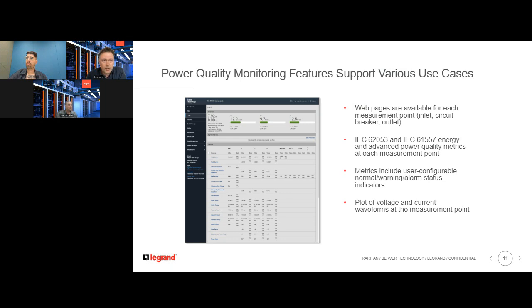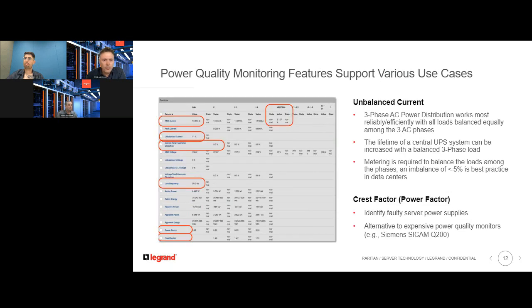Warning and alarm thresholds can be defined for every measurement parameter. And if thresholds are reached, the PDU can send these alerts over various data protocols. And Calvin has already talked about the waveform capturing feature, which is another available tool to visually inspect the power quality on the inlets and also on the outlets. So here you can see the magnified web user interface section, which shows the available measurement parameters on the AC inlet side. In the interest of time, let me just focus on two potential use cases for the measurement data.